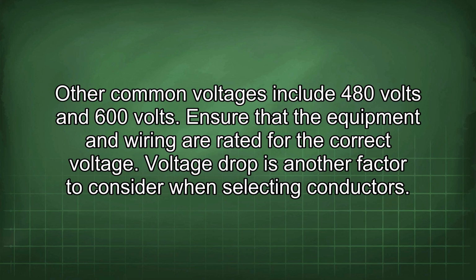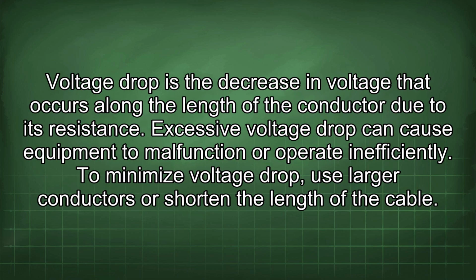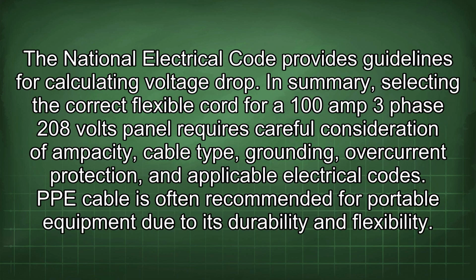Voltage drop is another factor to consider when selecting conductors. Voltage drop is the decrease in voltage that occurs along the length of the conductor due to its resistance. Excessive voltage drop can cause equipment to malfunction or operate inefficiently. To minimize voltage drop, use larger conductors or shorten the length of the cable. The National Electrical Code provides guidelines for calculating voltage drop.